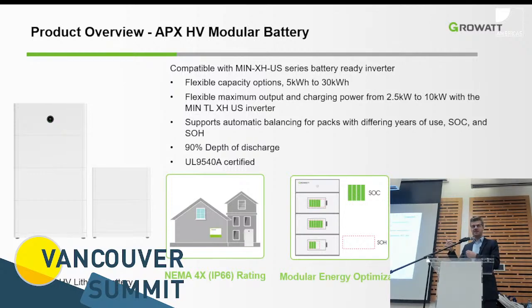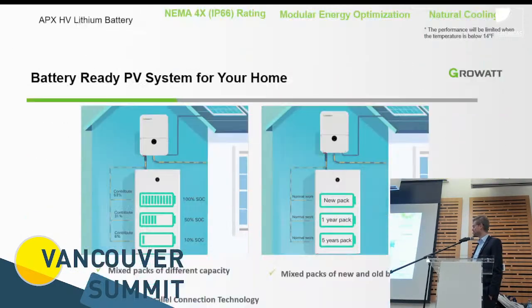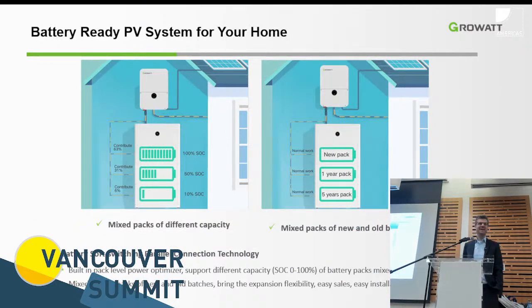So you're restricting that newest module that you put into that string, similar to a battery series connection. But in this case, with that parallel setup, it doesn't do that. And it's fully passively cooled, so the battery module with its surface area is just radiating into the room if it needs cooling, and the power stage on the side has a little heatsink under a little cover. So the DC to DC stage, consider it as a little mini optimizer for the battery, is cooled on the side. Exactly, and I already jumped ahead with my part, that you can easily mix and match different packs based on that separation from the cell to the outside system.